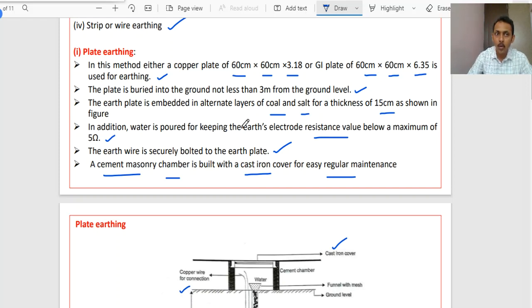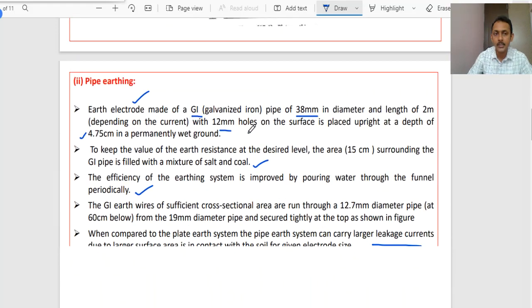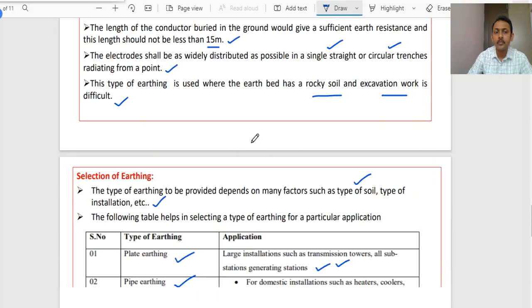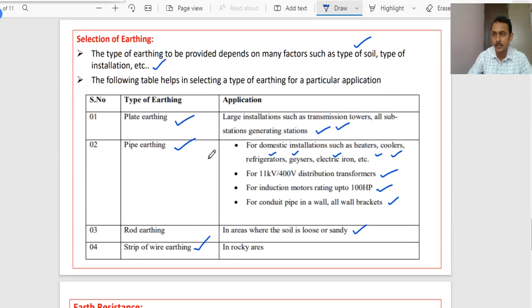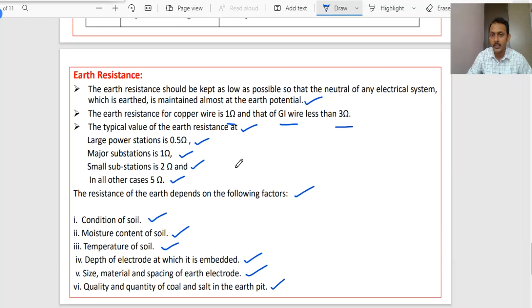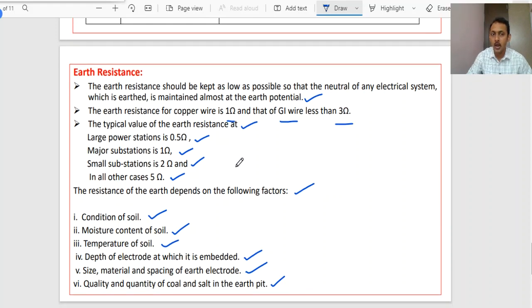So if there is no proper earthing, it leads to a severe shock to persons. A proper earthing system should be there, right? We have also discussed which type of earthing should be preferred for which application, depending upon the nature of the soil. If the soil is sandy or loose in nature, rod earthing is preferred. If the surface is rocky, then wire earthing is preferred. Now, earth resistance: how much should the numerical value be, and what should the minimum value be?